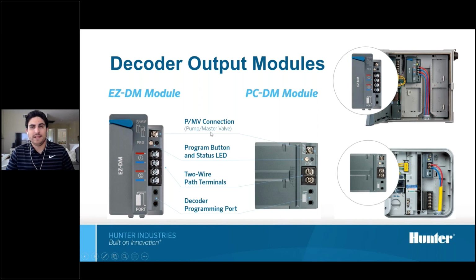One thing I like to discuss when bringing up Hunter 2-wire decoder systems is that we do it a little differently than some competitors. We actually program the station number into the decoders and address them individually. The big benefit is we have the ability to change a station address, set it as whatever we want, or keep it as we want in the field. So we're not pulling decoders back to the clock and entering big long serial numbers for each station. It's much cleaner and neater to be able to program the station number into the decoder.